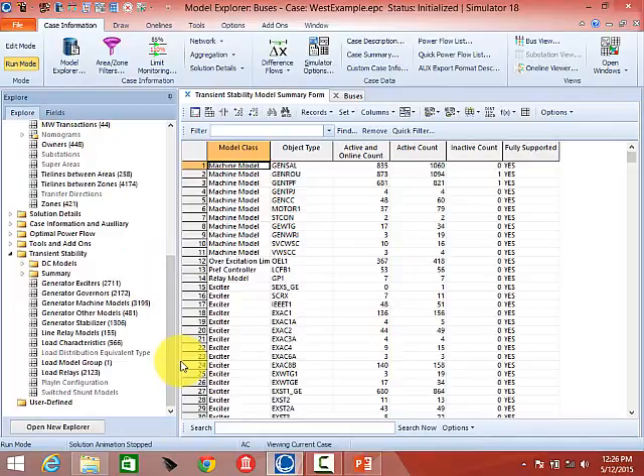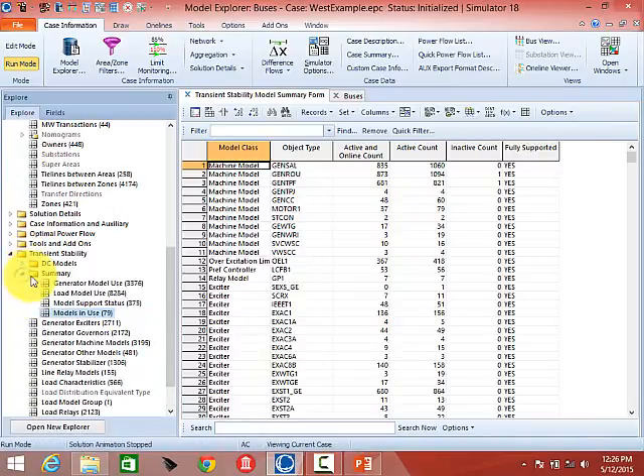Scroll down on the Model Explorer towards the bottom and you will see a tab for Transient Stability. Click on Transient Stability and it opens up that tab showing transient stability information — generator machine models, exciter models, governor models. First, click on the arrow next to Summary and open up the Summary, which provides a summary of what you've got in the case: generator model use, load model use, model support status. The first one we want to go to is Models in Use.